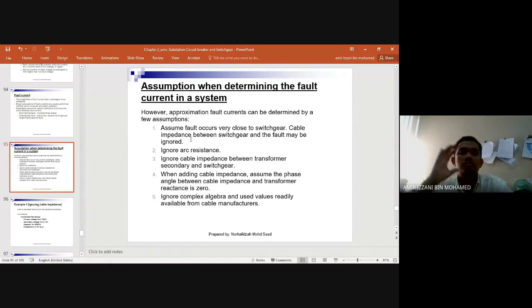Okay, switchgear, fault, very close, so we can ignore it, due to the short distance between this fault location and the switchgear. Ignore arc resistance. If we consider the arc as a conductor, it must have at least very little resistance, but we can ignore it in the system.